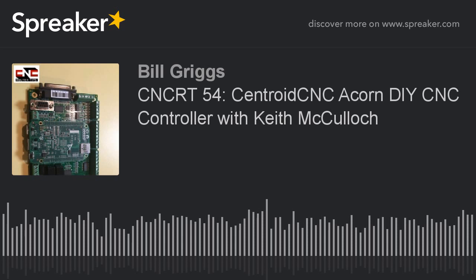So the Acorn board came from combining the MPU11 and GPIO4D boards into one board, kind of like the same theme as the all-in-one DC. Well, if we can get all these components onto one board, that means it's easier to install. There's fewer components, fewer cables, less wiring, fewer power supplies, because it's all on one board. The big difference between the all-in-one DC and the Acorn board is that the all-in-one DC, as the name implies, is made for DC servo motors, and the Acorn board is made for AC brushless servo motors.